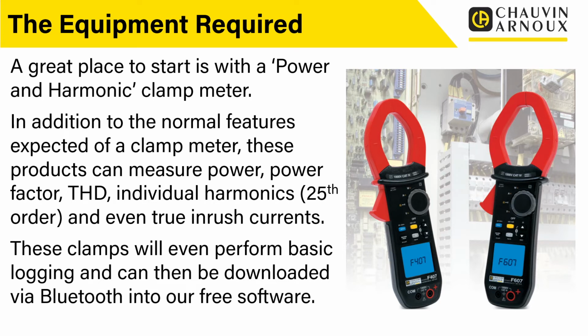We also talked about the fact that many clamps don't actually measure the current from harmonics. So if you're measuring the current in a cable, most clamps will clip off pretty much all of the current that's in the harmonics. They just look at what's in the fundamental, or a very narrow band of frequencies either side of the fundamental. So this will actually give you a real picture of the actual current that's flowing. And in the case of these meters, they'll actually give you individual harmonics. You can scroll through the individual harmonics and see how much current and what percentage of the fundamental that current is, which is really, really powerful.